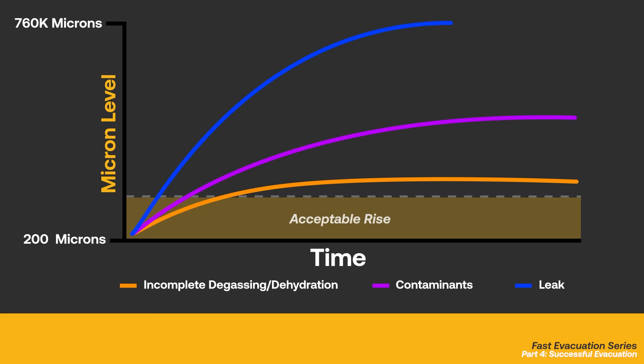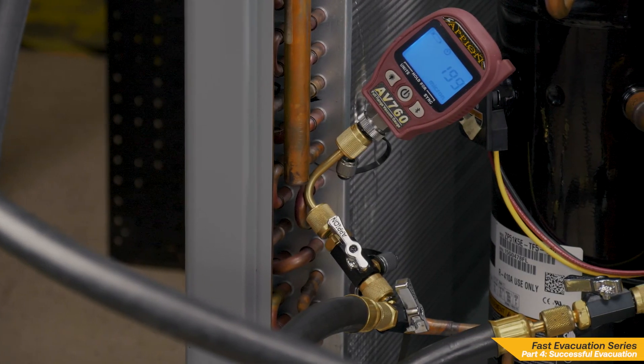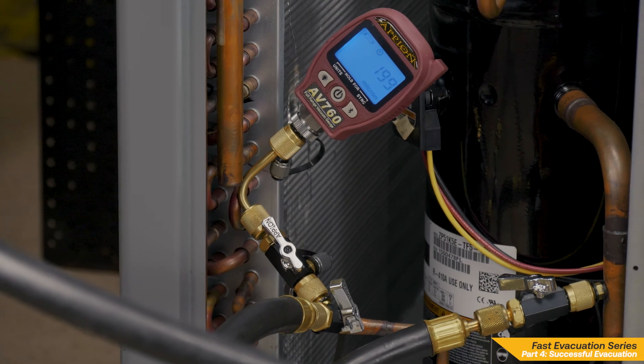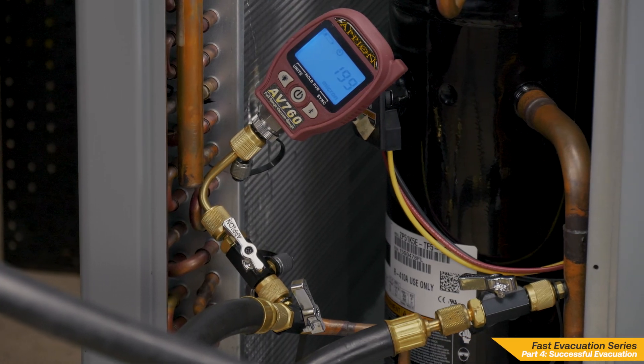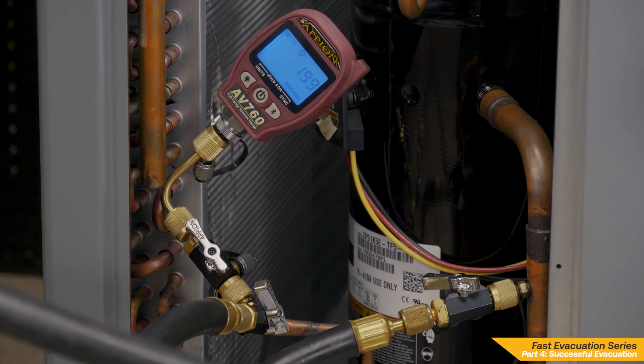Again, it's normal to see a rise during a decay test. Using a full range vacuum gauge will help you diagnose the vacuum and better understand what is happening inside the system. Once the issues have been addressed, another decay test must be performed. If the system successfully passes the decay test, the evacuation is deemed successful.